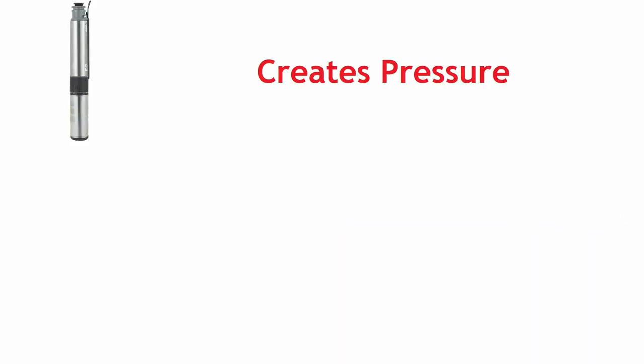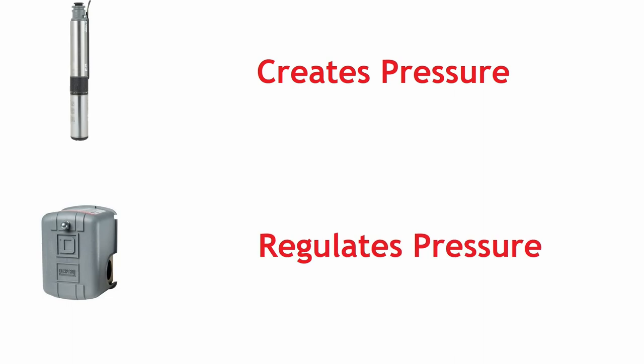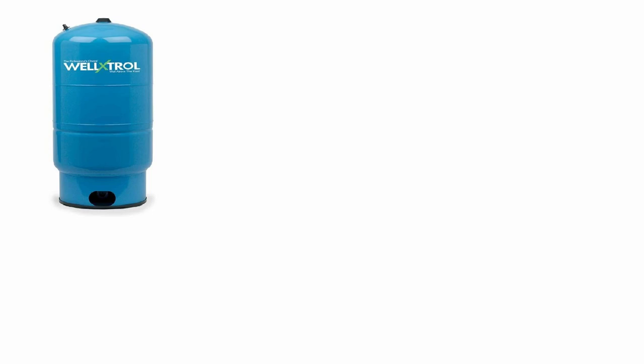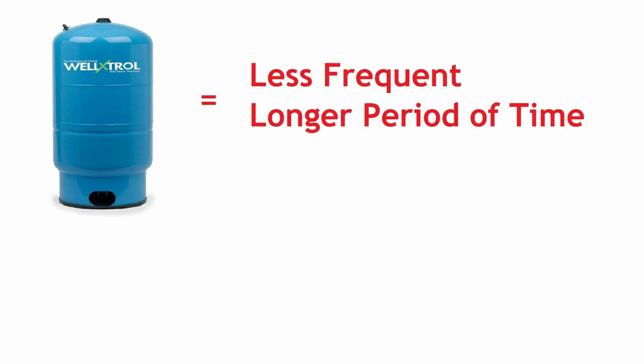The pump creates pressure and a pressure switch regulates the pressure. What the tank does is regulate the cycle duration and frequency. For example, with a bigger tank the pump will run less frequently and for a longer period of time.